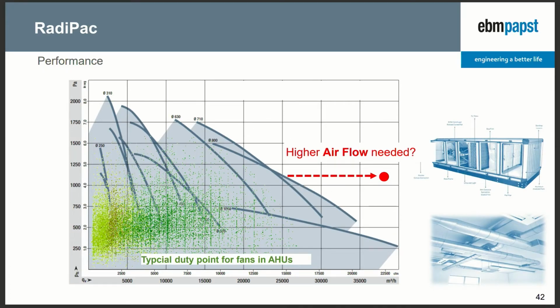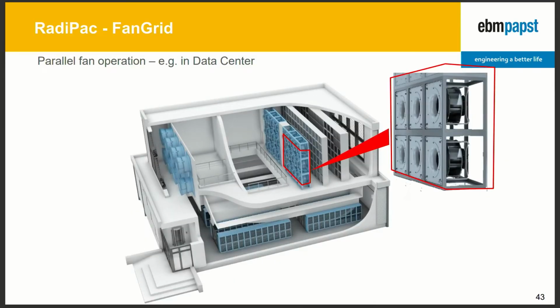Good. High pressure we covered. What about high volume? When you have applications where you need much more air, you can just multiply by operating the fans in parallel. This is shown here in an example of a data center. This can be done with axial fans or with centrifugal fans in a so-called fan array or fan wall. And this keeps the overall efficiency. So if the single fan has 70%, all the fans together will also have 70%.